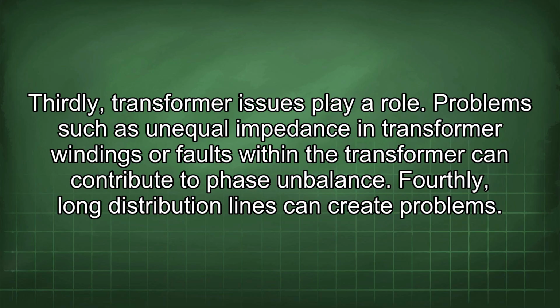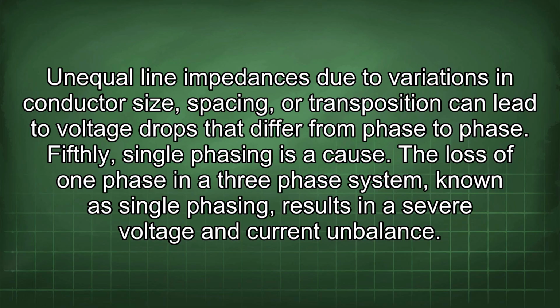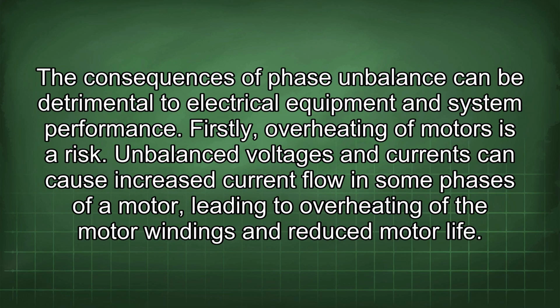Thirdly, transformer issues play a role. Problems such as unequal impedance in transformer windings or faults within the transformer can contribute to phase imbalance. Fourthly, long distribution lines can create problems. Unequal line impedances due to variations in conductor size, spacing, or transposition can lead to voltage drops that differ from phase to phase. Fifthly, single phasing is a cause. The loss of one phase in a three-phase system, known as single phasing, results in a severe voltage and current imbalance.